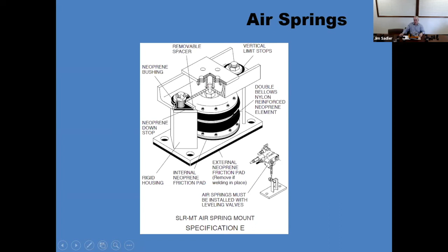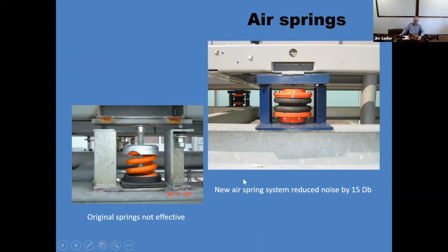So as an example of that, this shows a project in Chicago. They had an air-cooled chiller above a very high-value condominium. Initially, it was on steel springs shown on the left. They weren't ours, but they were fine and would have met its specification requirement. But they had a terrible noise problem in the space below, in the condominium below. So we replaced the steel springs with air springs, and there was a 15 decibel reduction in noise in the occupied space right below this air-cooled chiller.